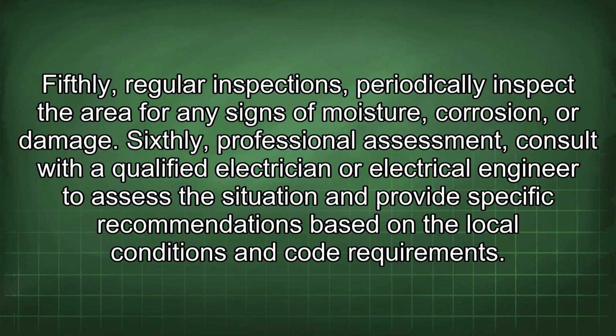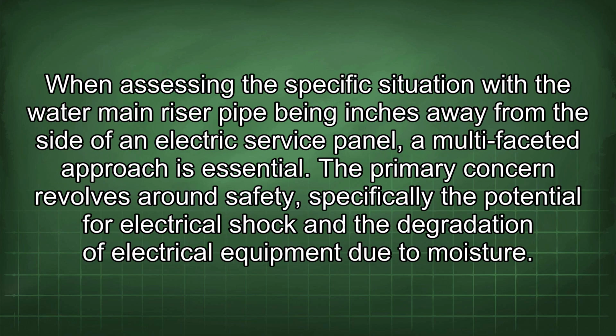Periodically inspect the area for any signs of moisture, corrosion, or damage. Sixthly, professional assessment. Consult with a qualified electrician or electrical engineer to assess the situation and provide specific recommendations based on the local conditions and code requirements. When assessing the specific situation with the water main riser pipe being inches away from the side of an electric service panel, a multifaceted approach is essential.